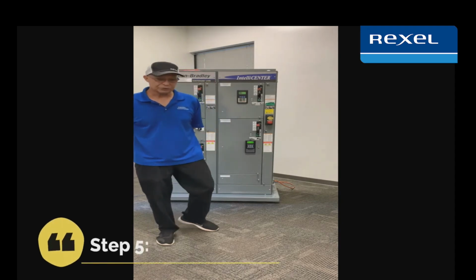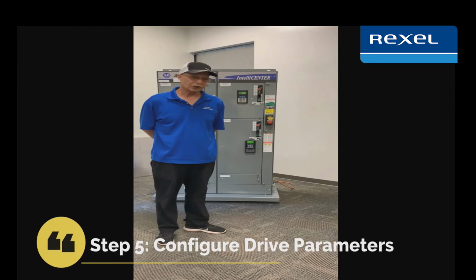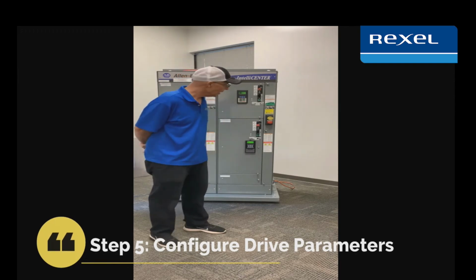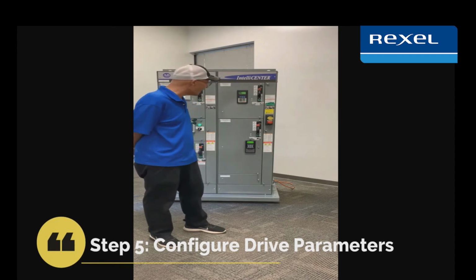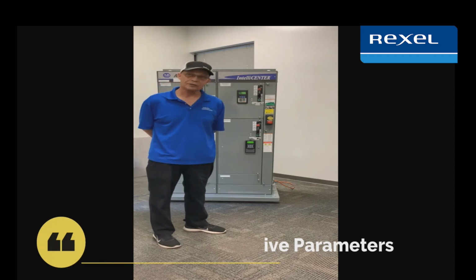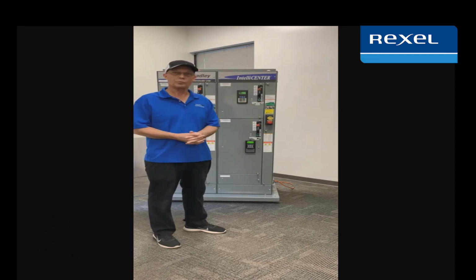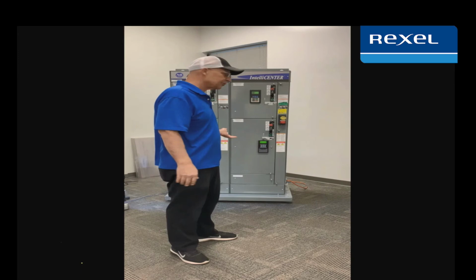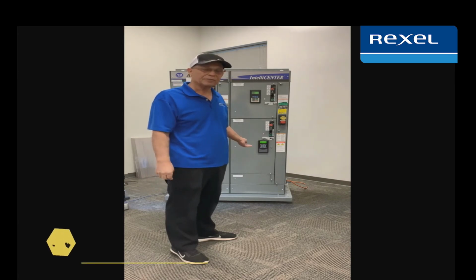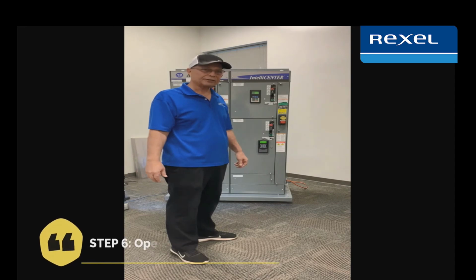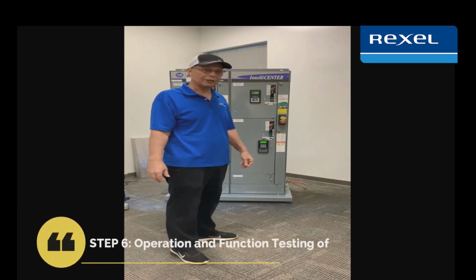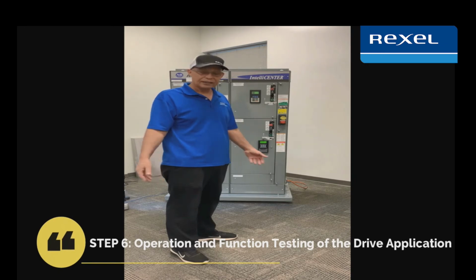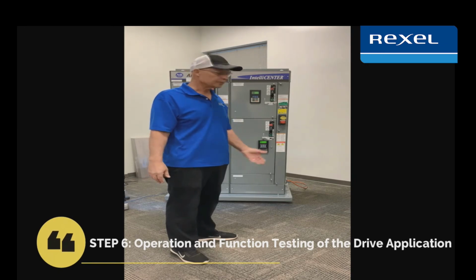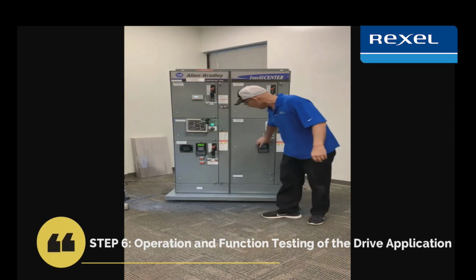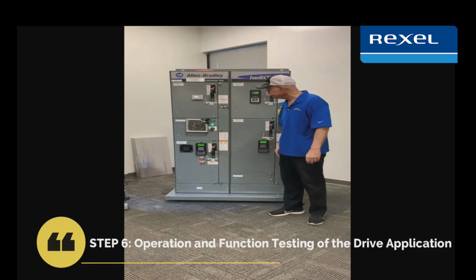Okay, after we're done with the pre-start inspection, we actually go into the startup. So we power the drive up, and now everything's checked out. We're set up to go ahead and start configuring the drive for all the parameters needed for the drive application. So for this application, the drive is being controlled from the HIM. In other applications that we had digital inputs that were push button selector switches, we would check those, including any PLC control. But for this application, it's the HIM. And I can start, and it does start, and it will stop.